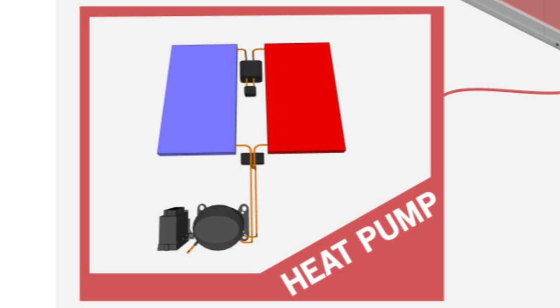Yeah, so that heat pump, any technician opening it up would see a compressor. It looks just like what they see in a room air conditioner or a refrigerator, and then connected to an evaporator and a condenser, or two heat exchangers. In our case, we use microchannels, so very advanced heat exchangers. And then it's an inverter drive compressor, about appliance scale. It's about a 400 or 500 watt compressor by Embraco. And then digital controls on the compressor speed, as well as the expansion valve, and then a reversing valve. So we can turn the evaporator into a condenser and vice versa on the other.